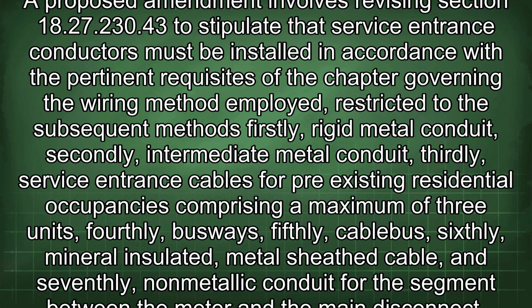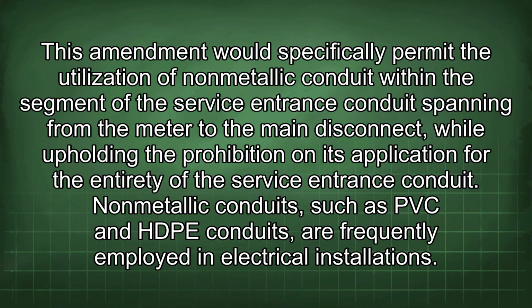the main disconnect. This amendment would specifically permit the utilization of nonmetallic conduit within the segment of the service entrance conduit spanning from the meter to the main disconnect, while upholding the prohibition on its application for the entirety of the service entrance conduit. Nonmetallic conduits, such as PVC and HDPE conduits, are frequently employed in electrical installations.